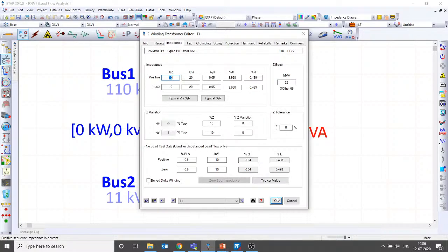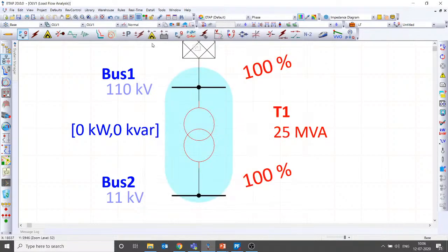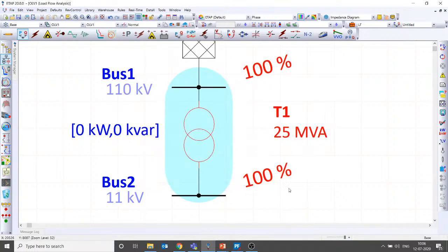You need to perform an unbalanced load flow. Unfortunately, as I told last week, we don't have that unbalanced load flow module, so we may not be able to simulate and showcase it. But if you have an unbalanced load flow, you can very well perform it. If you perform unbalanced load flow, then you will get the losses, like 10 kilowatt or whatever losses you have given. And of course, you have to enter these losses based on the data from the FAT, factory acceptance test, or the manufacturer guaranteed value before the FAT. So I think that's clear.